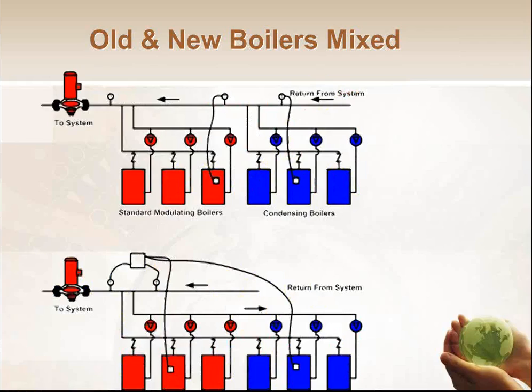Here's a couple other drawings. These are from our friends over at Bornquist. Some ideas on how you can pipe it. Like this one here on the top, once again, the key is as long as the condensing boilers see the return water first, I'm in good shape, because the colder the return water, the more efficient I am. It goes through 1, 2, or 3 of the boilers, however many it needs, and the water comes back up. If the temperature sensor says I'm warm enough, send it right out to the system. But if I didn't make my water set point yet, fine, come down here and run it through one of these other boilers, or 2 of them, or 3 of them, however many it takes to get me up to my set point. So that's a pretty easy way to do it.